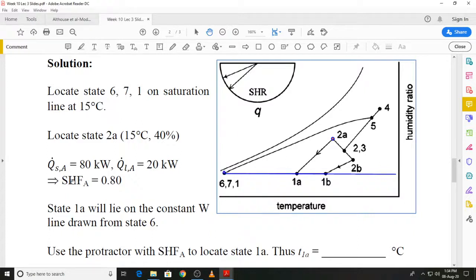Then, because we know the sensible heat factor for zone A, we can use the protractor, and on the protractor you will draw the line corresponding to a sensible heat factor of 0.8. I will just show it arbitrarily over here because this is not according to the data, this is just a general representation. So let's say this is 0.8, and what we have to do is draw a line parallel to this line from state 2A, and when you do that, it will intersect this line that we have drawn from state 6 at 1A, and that will establish state 1A on the psychrometric chart. So we can say that we have also located state 1A.